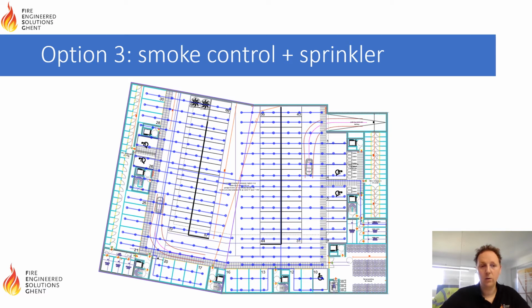The question is what to do when you have both a smoke heat control and a sprinkler system. Basically, you would still need to put your sprinkler system in according to European standards, and then the smoke heat control, according to the standard, would still require a smoke-free access till 15 meters. And the question is: is it really necessary to have a smoke-free access till 15 meters, knowing that the average temperature would not be above 40 degrees? And second question: is it really necessary to have a smoke-free access, knowing that the fire would not spread once the sprinkler is activating?